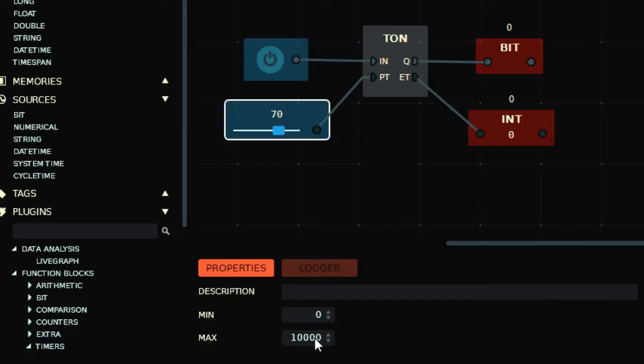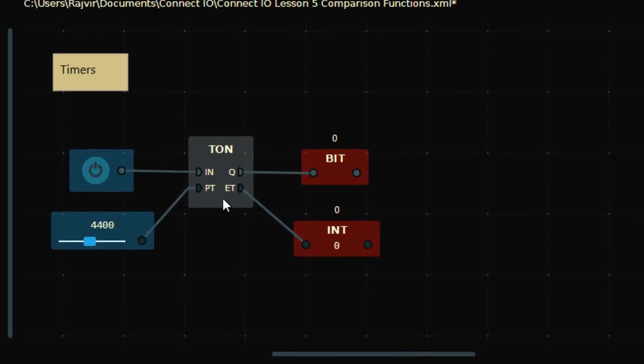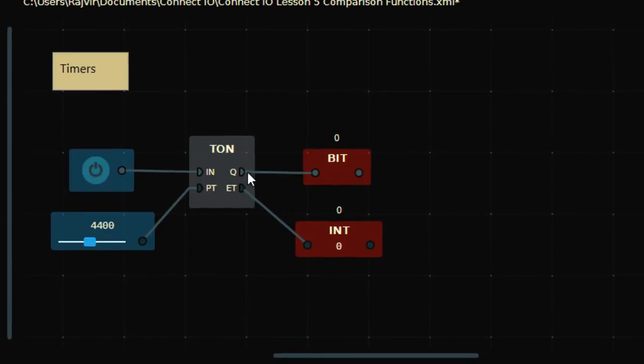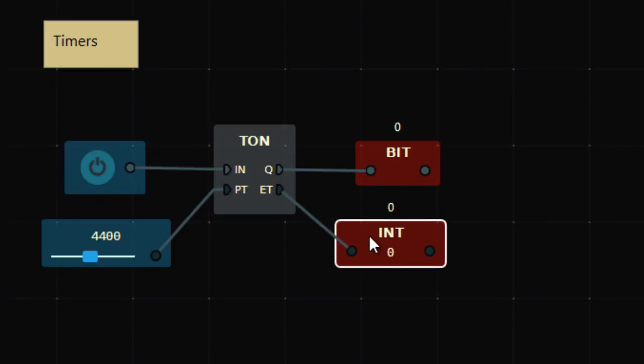This timer has a time base of one millisecond. So if I enter 4400 here, it means a delay of 4.4 seconds. The output will be ON after 4.4 seconds, and ET will show how much time has elapsed so far.